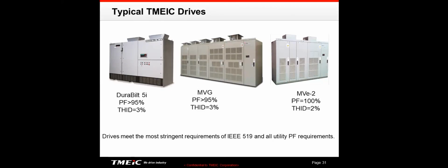Its power factor, we're talking about displacement power factor, is over 95%, and total harmonic current distortion maybe around 3%. The MVG is a different technology. We'll talk about it in a minute when we get into topologies. And again, you can see the power factor and the current distortion. The MVE2 is the most recent technology. It's got an active front end, and you can see it's got a power factor of 100%.